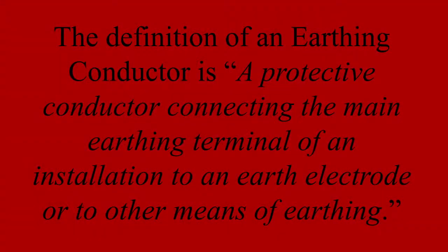Okay, so can we use the adiabatic equation to size that earthing conductor? I guess first of all, for confirmation, we'll tell people what we mean by that earthing conductor. So I'll just post up the definition. If we look in part 2 of our regs, it tells us that the earthing conductor is a protective conductor connecting the main earthing terminal of an installation to an earth electrode or to another means of earthing.